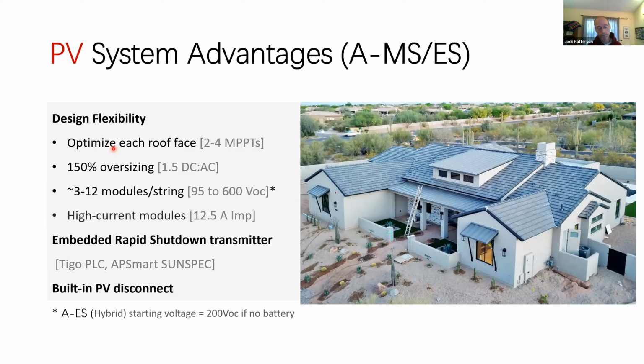So when you're viewing the performance of the system, not only getting optimization, you can look at the string level, what's happening. So you're effectively saying I can look at each roof face separately in the monitoring portal. Oversizing, I would say fairly standard, 150%. You need to be able to oversize, especially if you're doing east-west arrays. If you have roof faces like the one on the right, where there are a lot of different sizes, sometimes you get some small ones and you can only fit 3 or 4 modules. Indeed, you can do that because we have a low starting voltage requirement. You wouldn't want to design all your strings to be 3 modules. It would work, but it would be inefficient. So you would just do that for 1 or 2 strings.